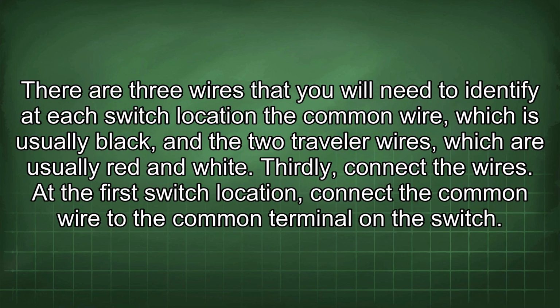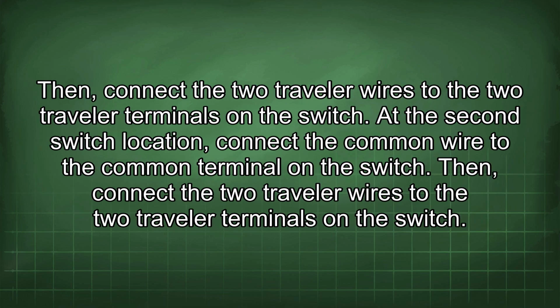There are 3 wires that you will need to identify at each switch location: the common wire, which is usually black, and the 2 traveler wires, which are usually red and white. Thirdly, connect the wires. At the first switch location, connect the common wire to the common terminal on the switch. Then connect the 2 traveler wires to the 2 traveler terminals on the switch. At the second switch location, connect the common wire to the common terminal on the switch. Then connect the 2 traveler wires to the 2 traveler terminals on the switch.